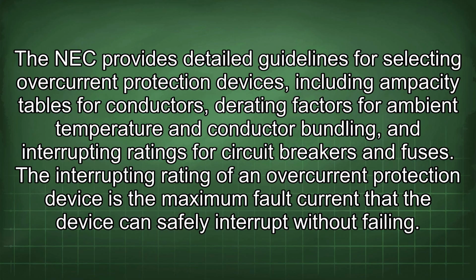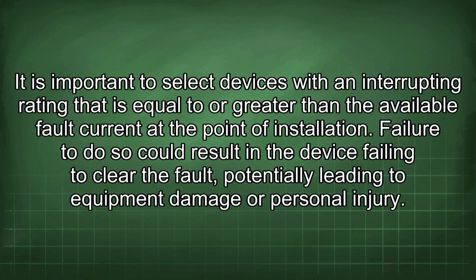The interrupting rating of an overcurrent protection device is the maximum fault current that the device can safely interrupt without failing. It is important to select devices with an interrupting rating that is equal to or greater than the available fault current at the point of installation. Failure to do so could result in the device failing to clear the fault, potentially leading to equipment damage or personal injury.